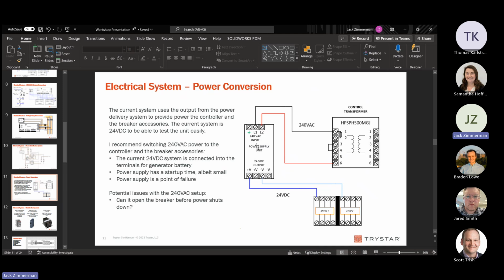But for this generator issue we're talking about, where it kicks up in a failure, I would like to be able to have this thing always stay on no matter what, which is the goal through the use of the genset battery. So I don't want to take up that slot. Because there's two power supply sources to this controller. One's AC, one's DC. We're taking up the DC one right now, which is also the one you would connect the generator battery to. As well as that, the power supply has a startup time. It's a really small startup time, but we can just wire 240 volt AC to the controller and then run the rest off of 24 volt DC.